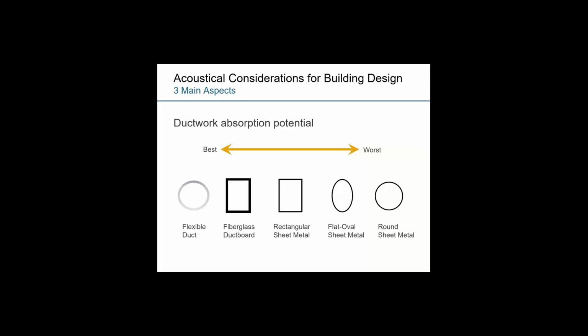Ductwork itself often has different potentials of absorption and sound transmission. There's many different types of ductwork that's used, obviously, to transmit air and heat and cooling. But in general, flexible or fiberglass duct can have a better absorption potential than a sheet metal duct. And as you move through sheet metal duct from a rectangular to an oval to a round sheet metal duct, it will transmit sound quite easily without having it break out or break through or be absorbed into the material itself.